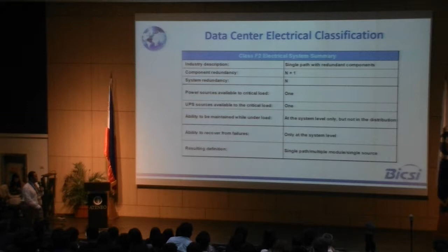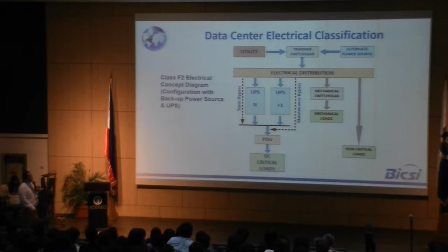So when you put them in parallel, this is your load—say your load is 1 kilowatt. What rating should your UPS be, 500 or 1 kilowatt? 1 kilowatt, so they share at 50% each. When one goes down, the load can still be served. So that's the concept—basically a typical parallel circuit.